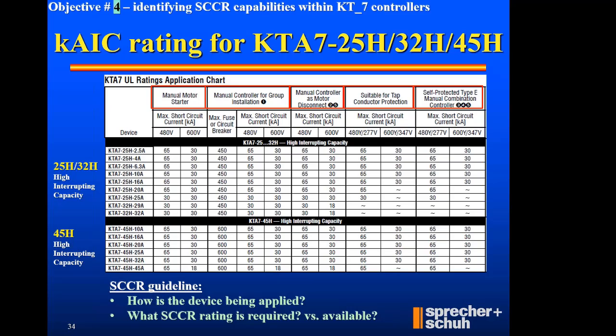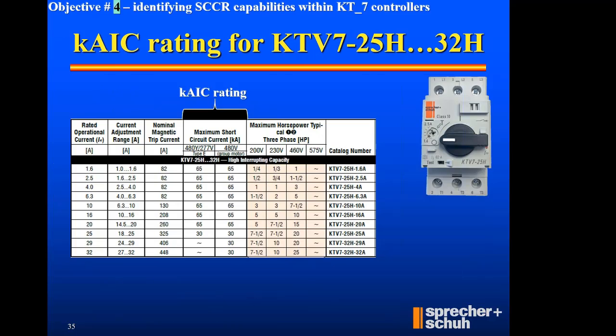So up to now, all we've talked about is the controller itself. And being that we're talking about controllers themselves and KAIC rating, let's flash up that KTV, as in Victor, 7, and see what kind of KAIC approval I can get on a KTV product. I'm looking down here at a 25, that's going to give me a current adjustment range of 18 to 25 on that FLA dial. So yeah, I can still get 30 KAIC under a 480Y situation.